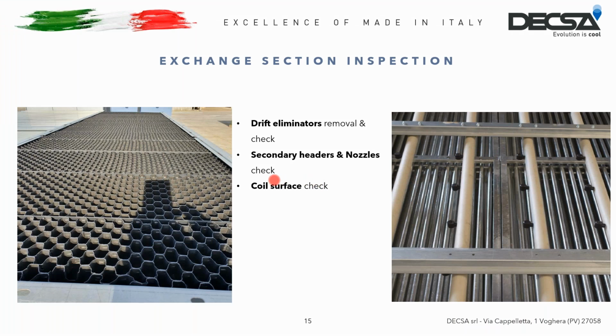Once you reach the drift eliminators, you need to remove them manually in order to check that there is no dirt or limescale inside them, which would compromise their efficiency. And then, always with the water system running, check that the water sprayed by the nozzles is evenly covering the surface of the exchange coil and the surface itself is clean. If not, it's necessary to manually remove the secondary headers, the pipes to which the nozzles are connected, bring them to the ground and clean them with a pressure lance. If this is not enough, they must be replaced.